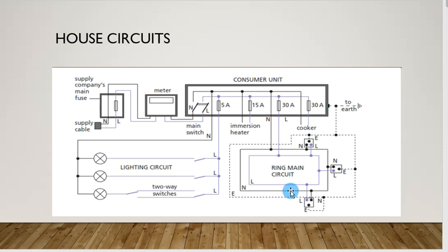As we said earlier, if you use a thin cable and you are drawing a large current through it, it will get heated up, because thin cables have higher resistance. If the current increases through them, they can get hot and they can cause a fire. That is overloading of the cable. So you have to ensure that each type of circuit has the correct size of wires used.